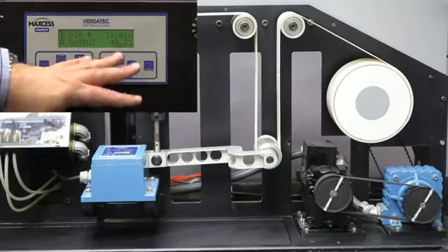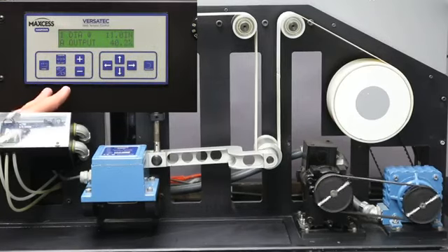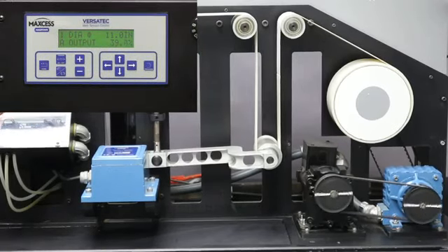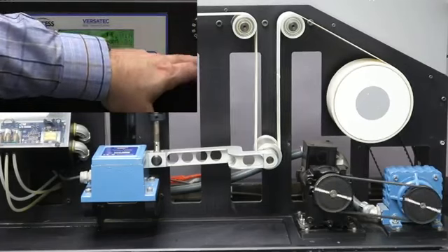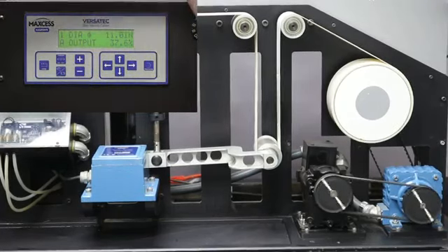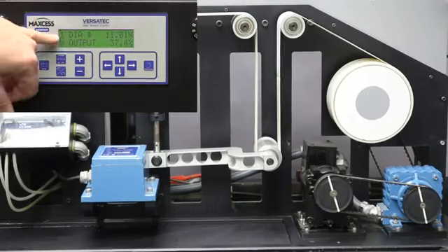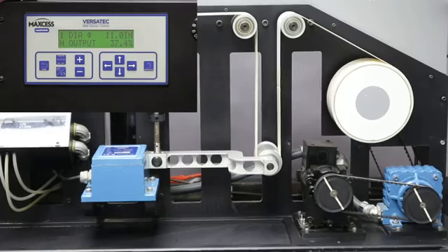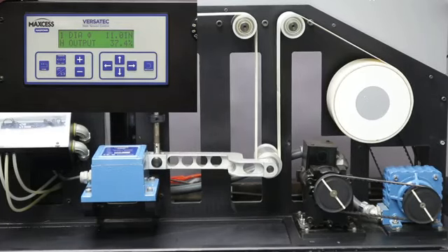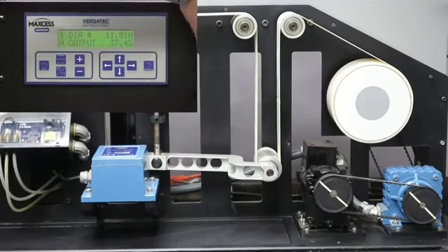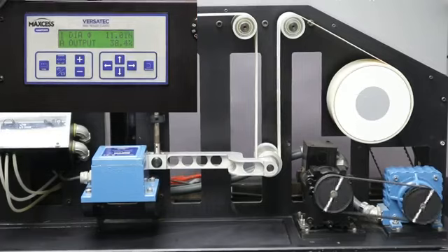So it's very important to connect what we call a run-stop connection on these. So rather than using the speed of the machine to stop the web, you should use a run-stop connection. In this case, we've got a switch here. And if you look at the screen, you can see it says A, which is automatic. When I hit that stop, it goes through a stop sequence and goes into hold. And what that did was it turned the integrator off, which pauses or holds the control loop. So now that I've used the controlled stop, when I turn it back on, I start right back off from that point.